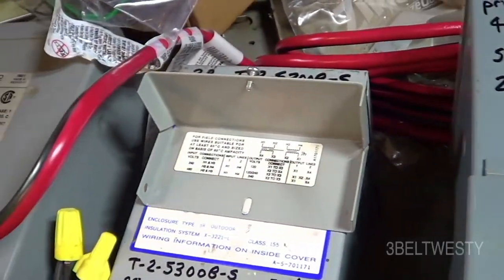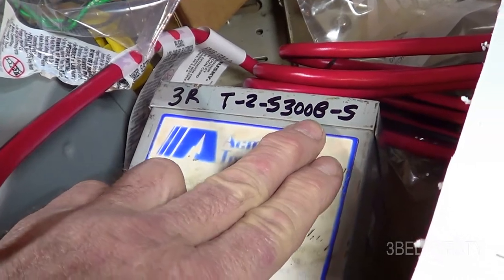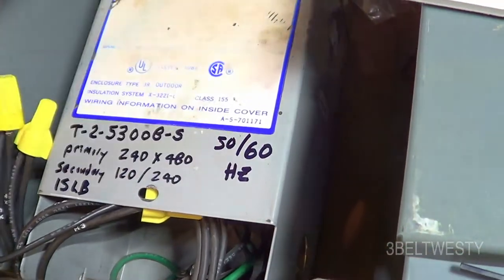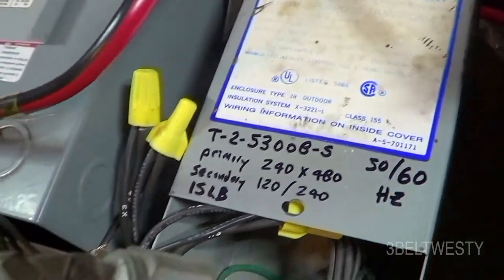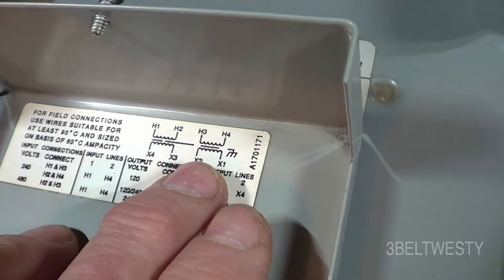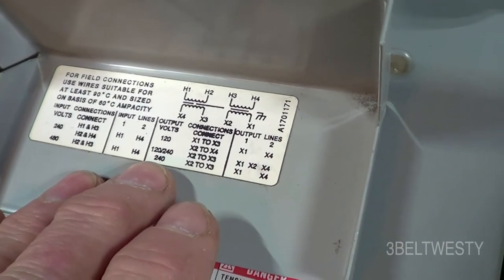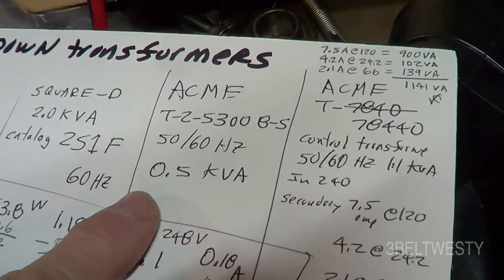This next unit is an Acme T-2-5300B-S, wired 240 in, 120 out. It's a 50/60 Hz model, so it has a bit more steel in it. The wiring diagram is inside the cover — inputs are labeled H's, outputs are X's. You can wire it for 240 or 480 input, or get 120, 240, or 120/240 output using the center tap.